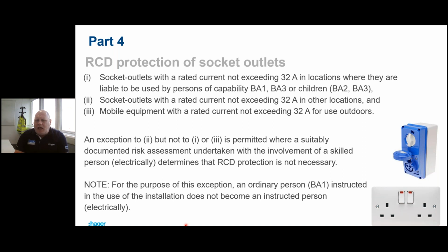So if it's going to be used by an ordinary person, it's got to have socket RCD protection. Sockets that aren't being used by an ordinary person and are being used indoors, we can apply a risk assessment. Okay, so we've got to be pretty careful around that one because this is pretty specific. A risk assessment, and the socket is not being used by an ordinary person. There's a note on the bottom there: for the purpose of this exception, an ordinary person, BA1, instructed in the use of the installation does not become an instructed person electrically.